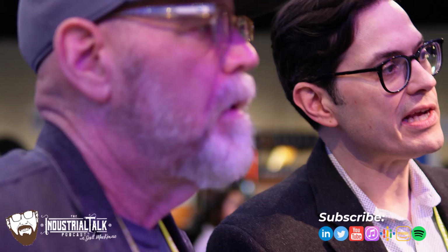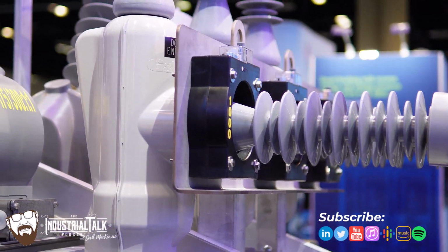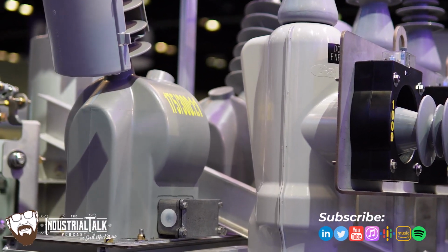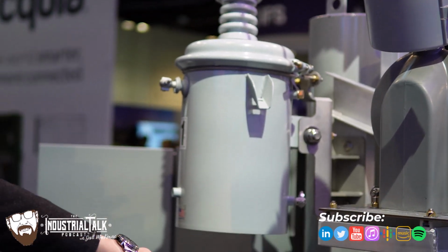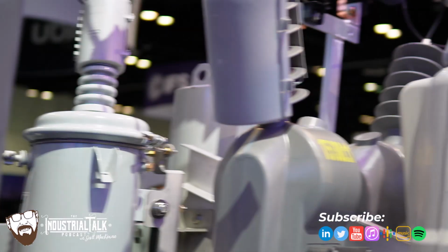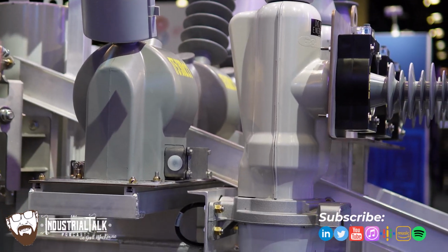So because of the unique construction of the Viper, this is a dead tank design module. I have the ability to bolt on accessories to this to be able to give you very high accuracy current and voltage measurement on the device. So I've got 3 instrument transformers for current here. I got 3 instrument transformers here for voltage, all being wired down into a socket for measuring energy using a recloser, which is commonly being used as a protection device. It's exactly correct. Right? But what you're doing is you're pulling the data, you're looking at the data, and you're getting that data in the way that is helping the grid manage the grid too as well.